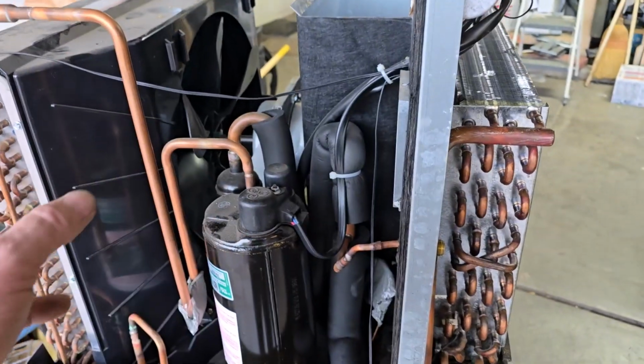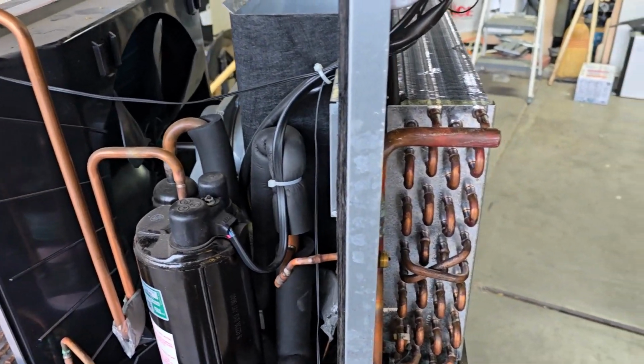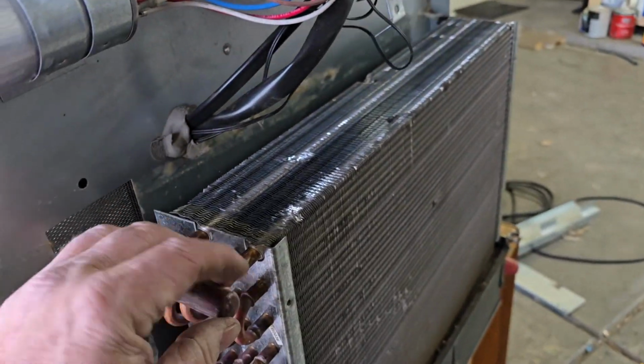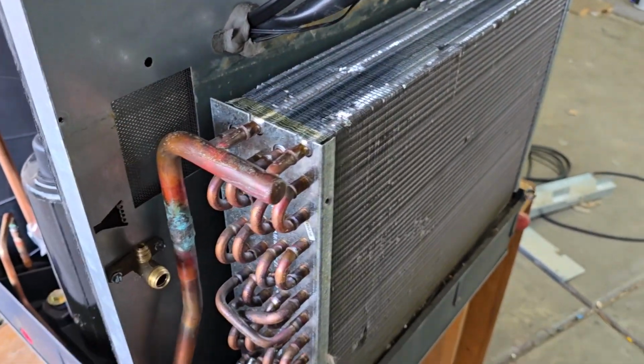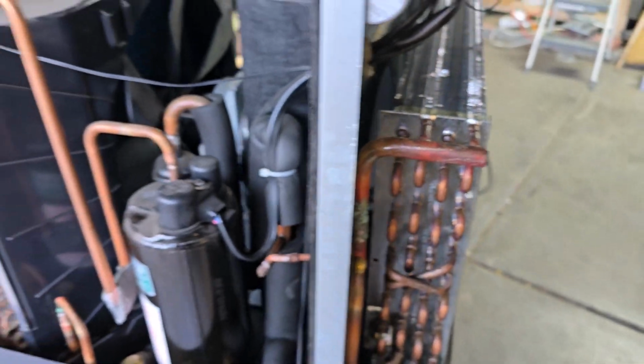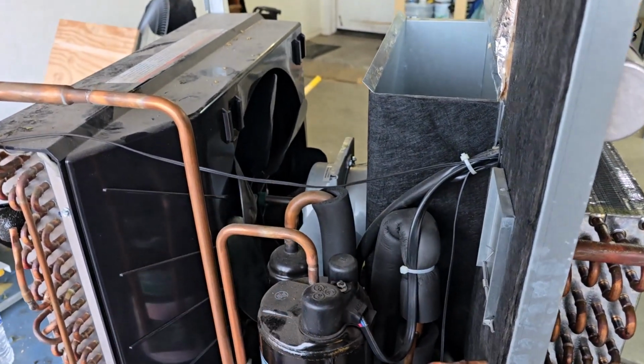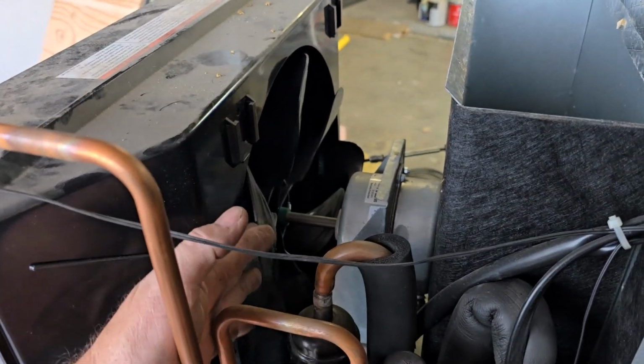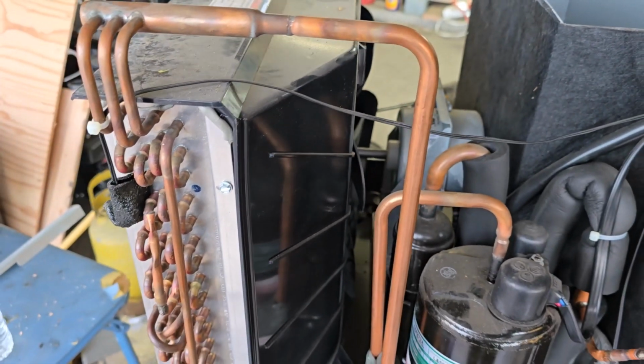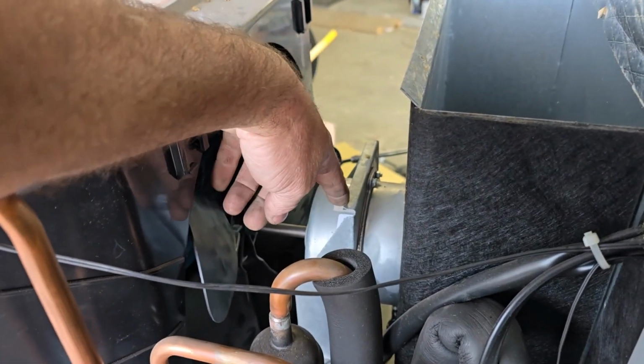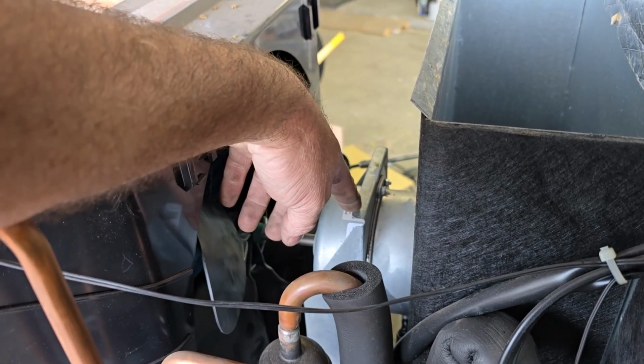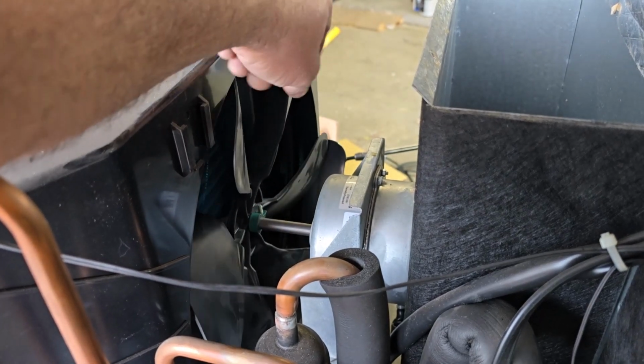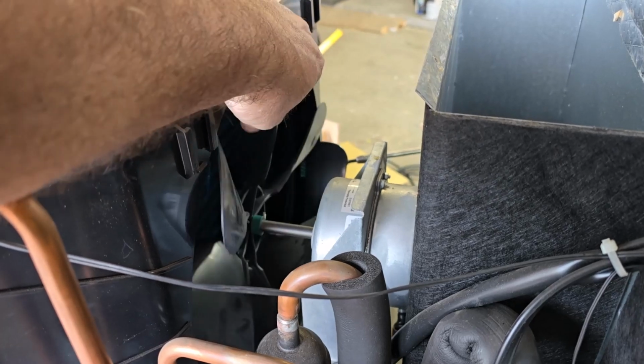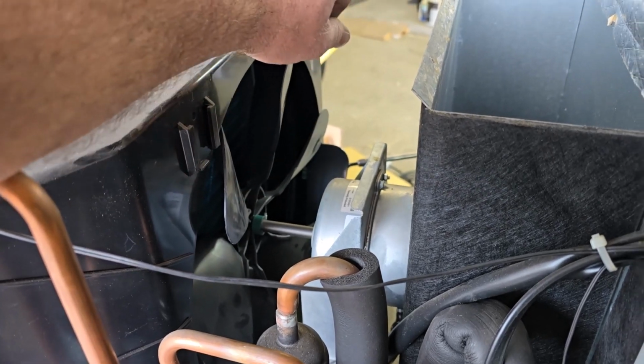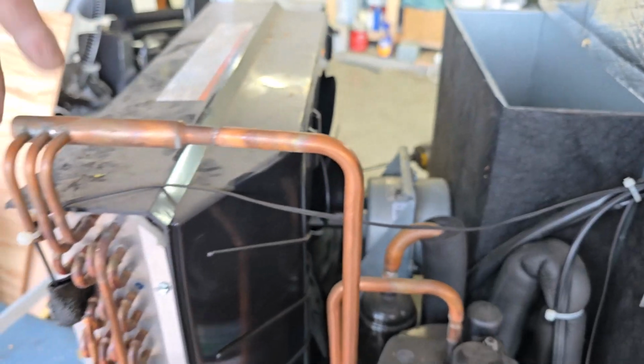I can use this one and get rid of that one, put the heat exchanger over there, but then I've got to put all this back together and seal it, and I already took that apart. But I kind of wanted to just have one axial fan out here to run that. This motor's made for the static of the blower going through a bit of duct work - I'd like to just probably put a smaller motor in here, but use it for an evaporator with no duct static.